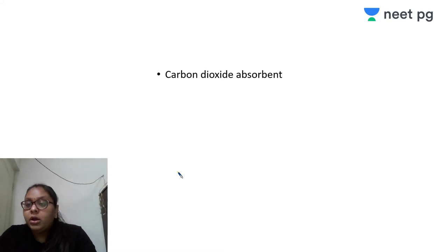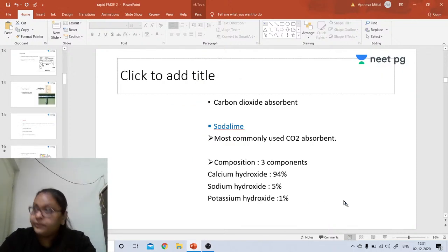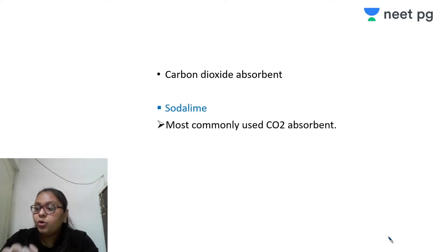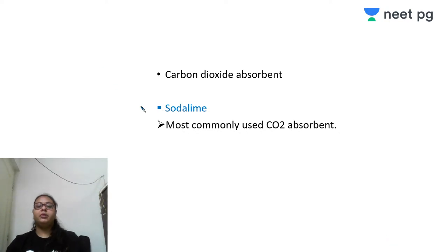Now, depending upon the carbon dioxide absorbent, the questions are asked. Okay, so depending upon the carbon dioxide absorbent, what is the most commonly used carbon dioxide absorbent? The most commonly used carbon dioxide absorbent is soda lime.